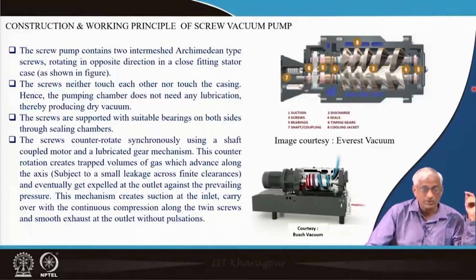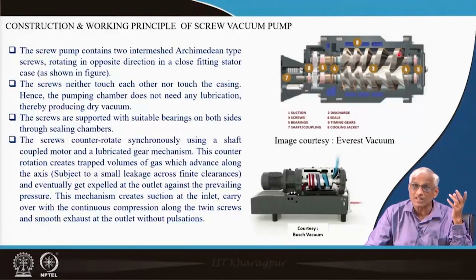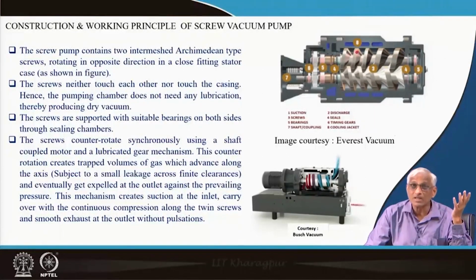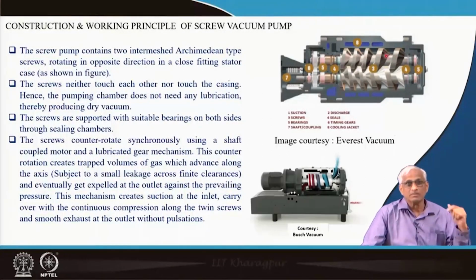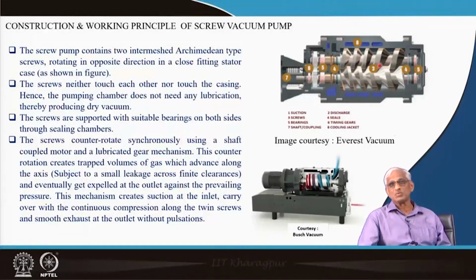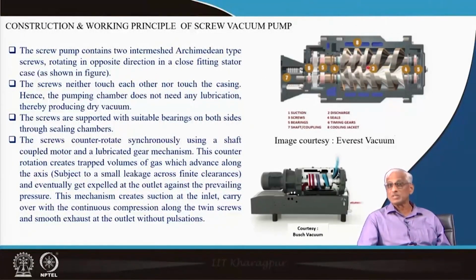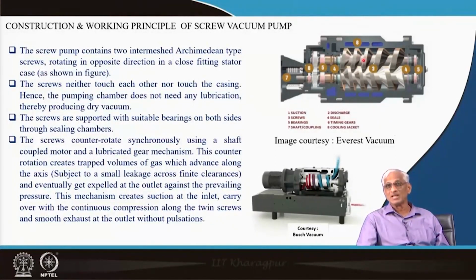So the screws neither touch each other nor touch the casing. Only then is it possible to produce high speed rotation, because there is no friction. Only then will you get good pumping speed, and only then will you get dryness, because if they are touching, you would need more cooling and lubrication.